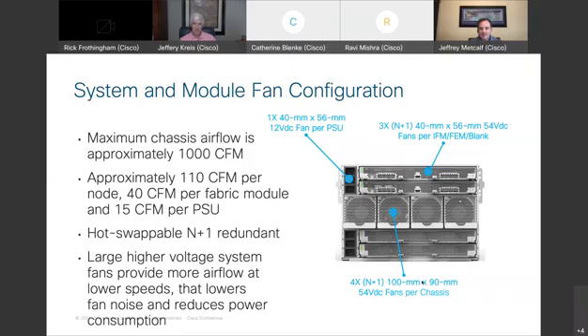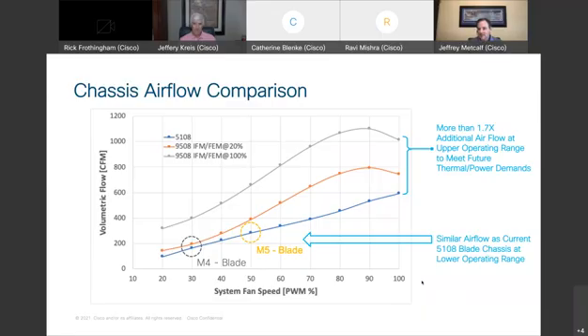Okay, next slide please. This is kind of a comparison of the airflow we talked about. If I just orient you to this chart, on the horizontal axis is fan speed, going from 10% to 100% PWM - think of this as 10% speed to 100% speed. On the vertical axis you have volumetric airflow, the volume of air going through the system.